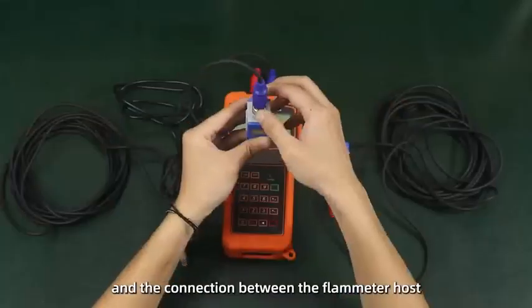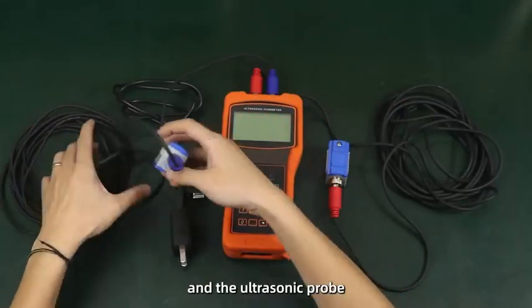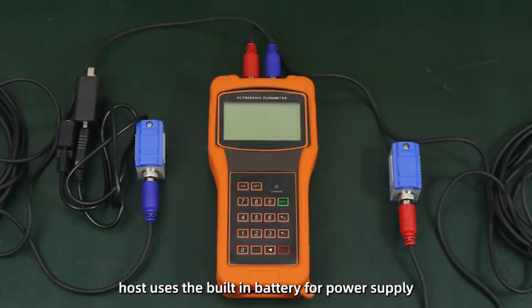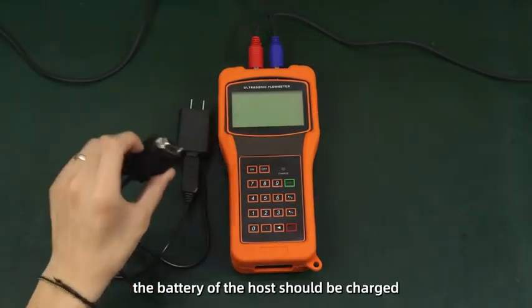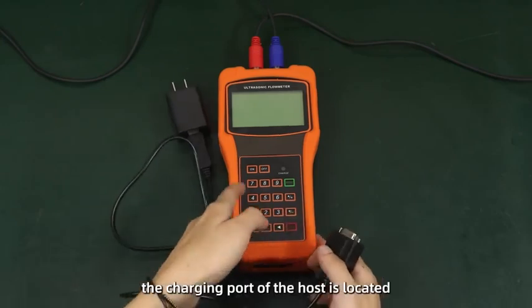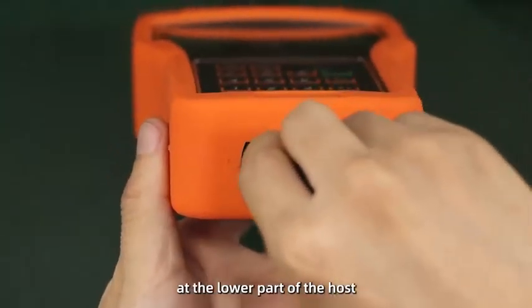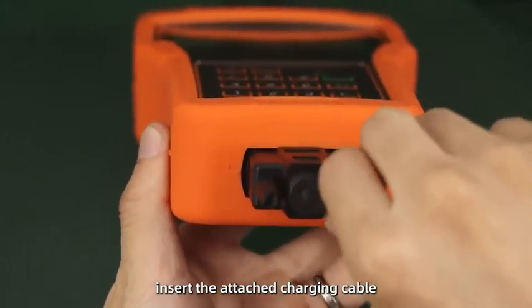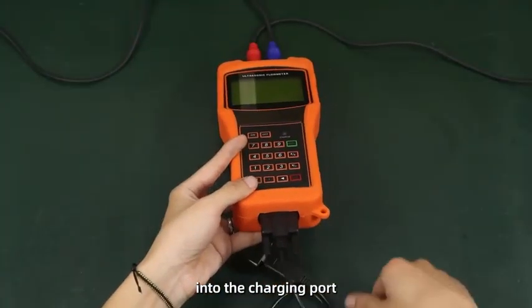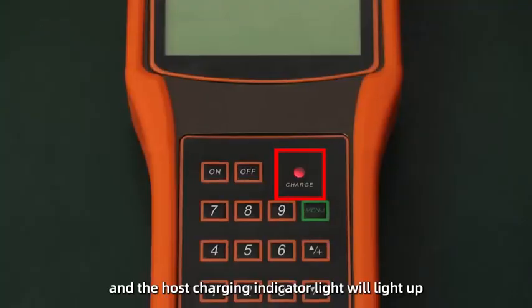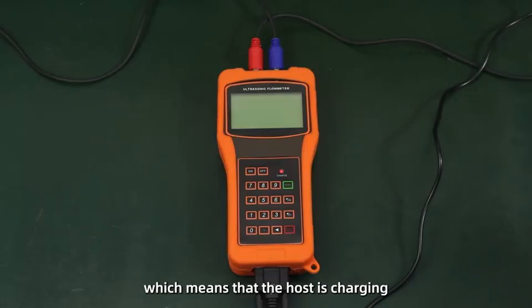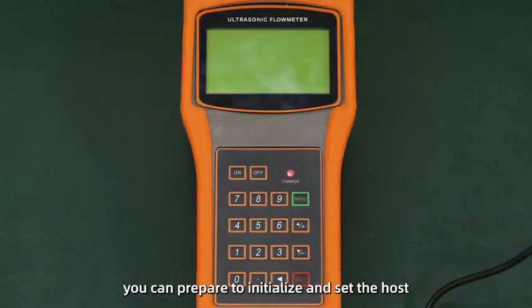And the connection between the Flowmeter host and the ultrasonic probe is completed after the connection is completed. Because the Flowmeter host uses the built-in battery for power supply, the battery of the host should be charged when it is used for the first time. The charging port of the host is located at the lower part of the host. Insert the attached charging cable into the charging port, plug in the power supply, and the host charging indicator light will light up, which means that the host is charging. When charging the host, you can prepare to initialize and set the host.